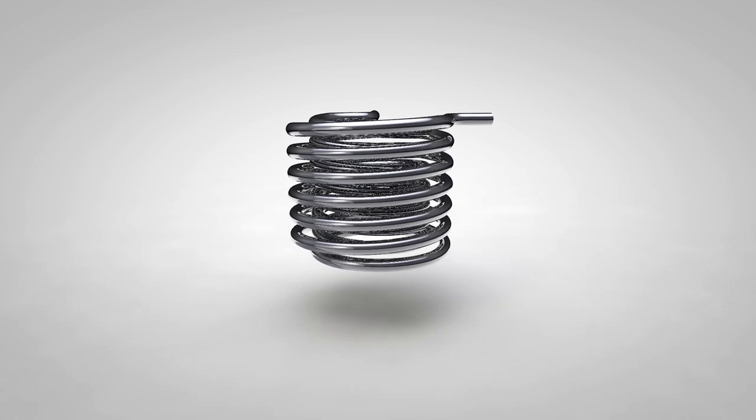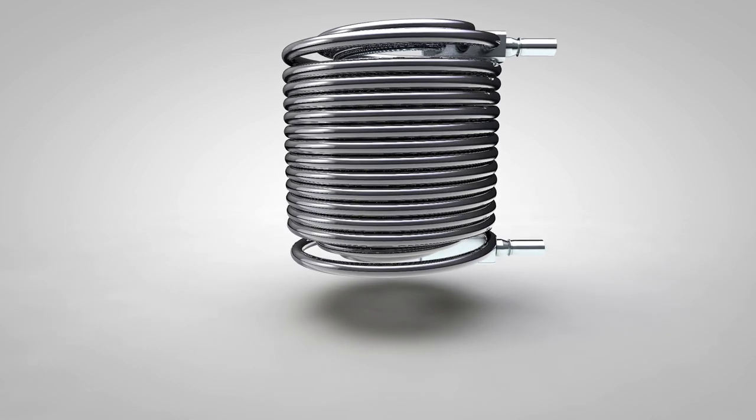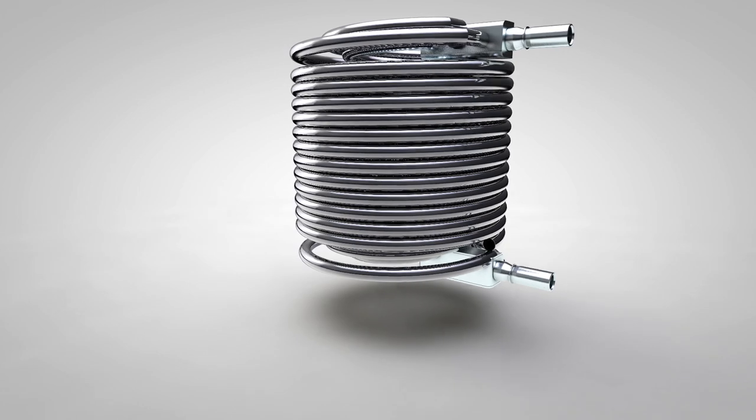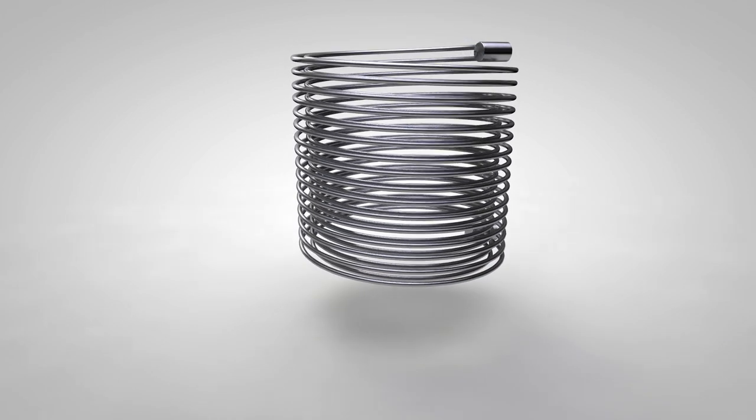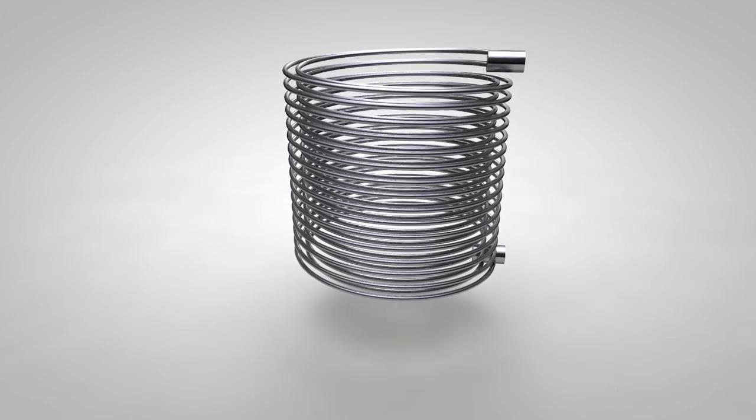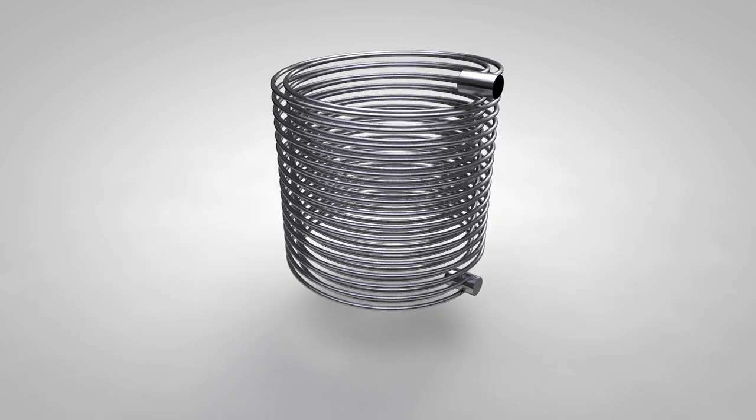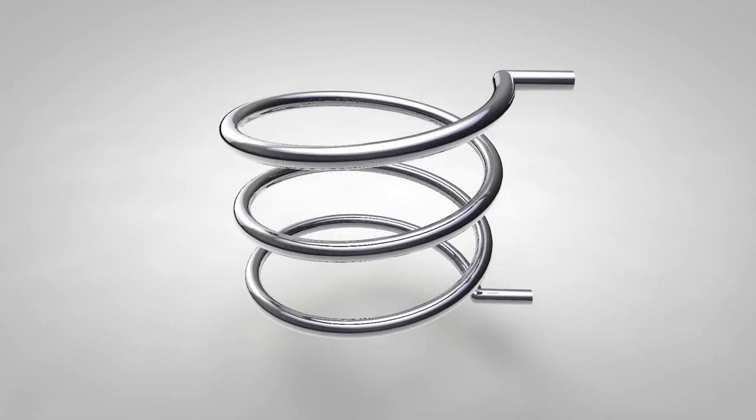Bear in mind, the kilowatt rating is only an indication of the maximum potential output. It needs energy from the heating system in the form of the right water temperature, flow rates, and pipe sizes in order to achieve it. The four most popular ways to increase the coil surface area.